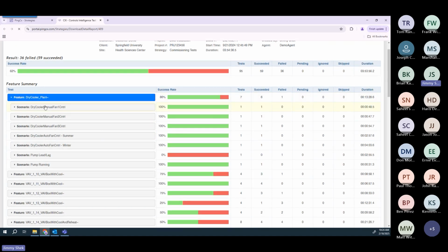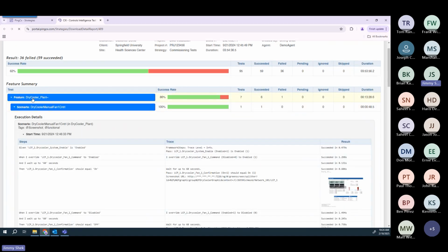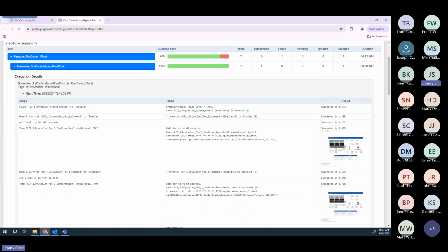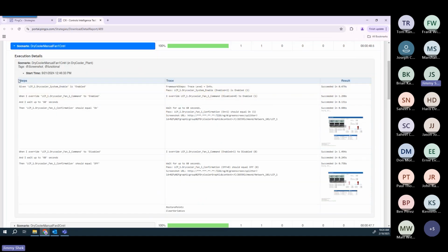All right, so let's take a look at the example for the dry cooler feature file and the first scenario, which was labeled as a functional scenario for the dry cooler fan 1 control. Again, on the left-hand side are the steps. So given that the dry cooler system is enabled, when I override the fan 1 command to be enabled, and I wait up to 60 seconds, then the expectation is that fan 1 confirmation should equal on.